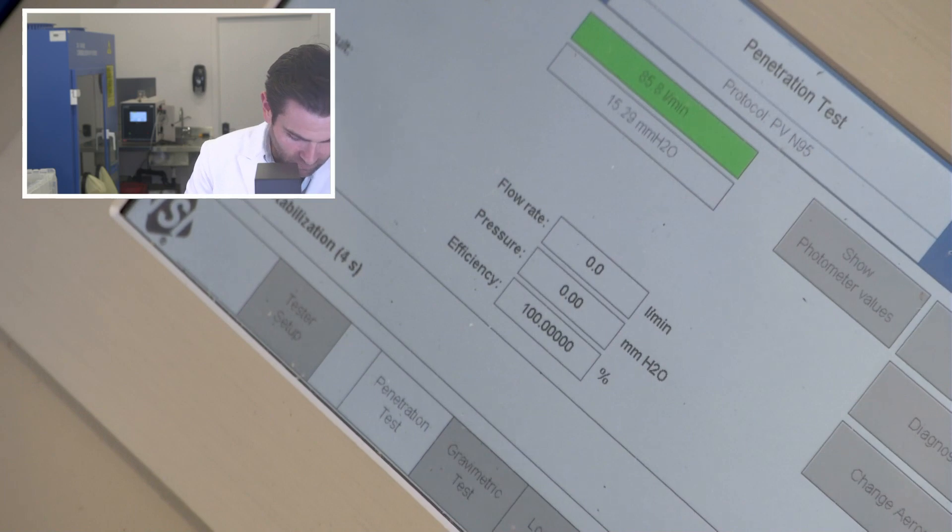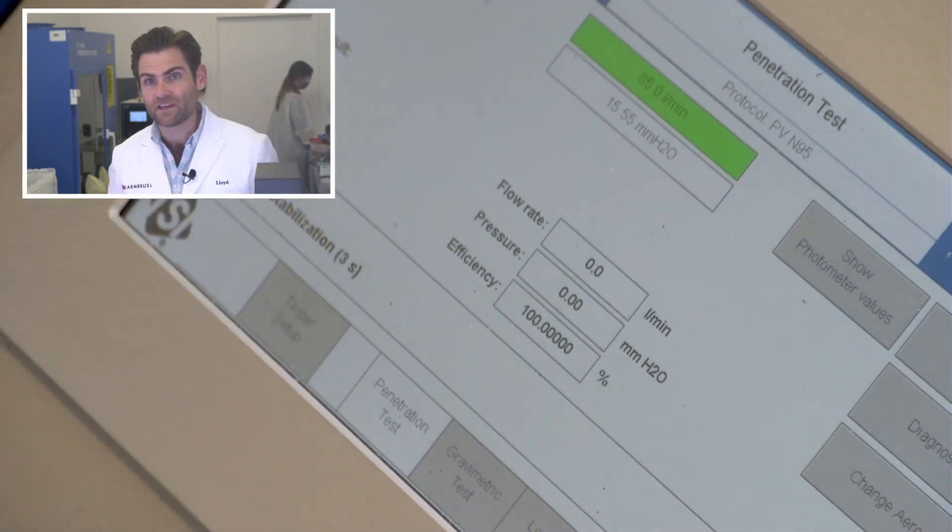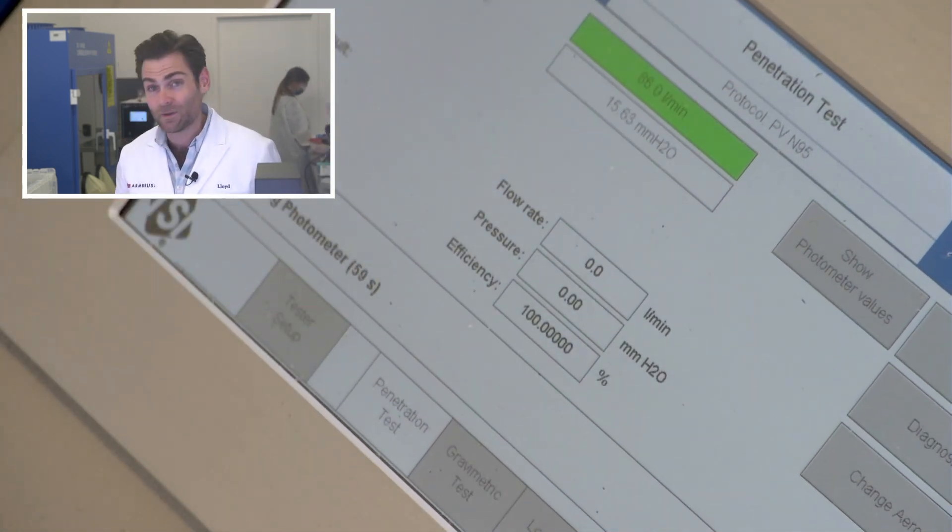And we're going. That's a good clamp — it's a near miss though. This is a PFE machine — Particulate Filtration Efficiency machine. We're testing the KN100 for the first time, although I'm told it's a pre-production sample, so if it fails we'll give them that. It's from a company called Lianzhi — a Chinese company doing the KN standard. It's the HXY 1002 KN100.